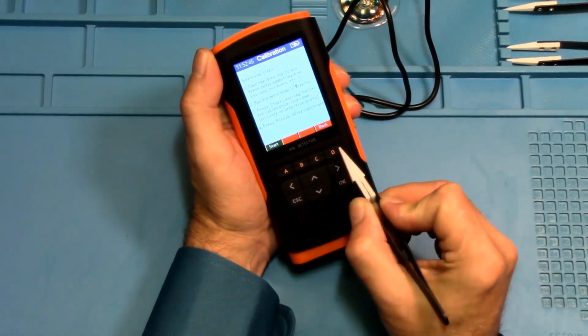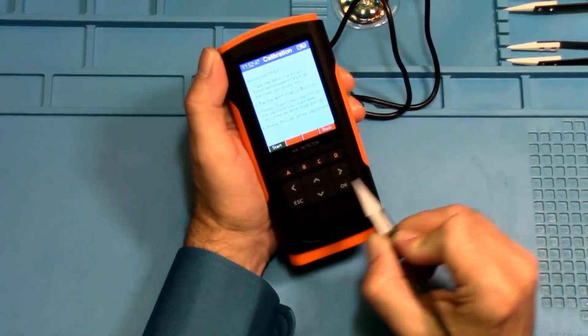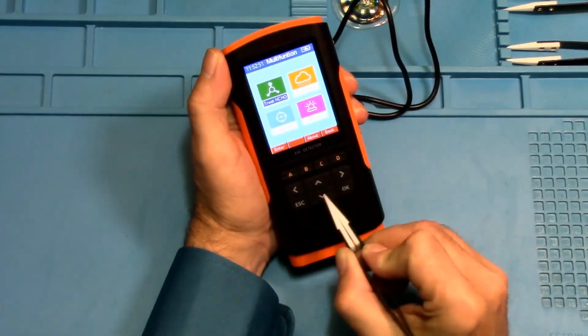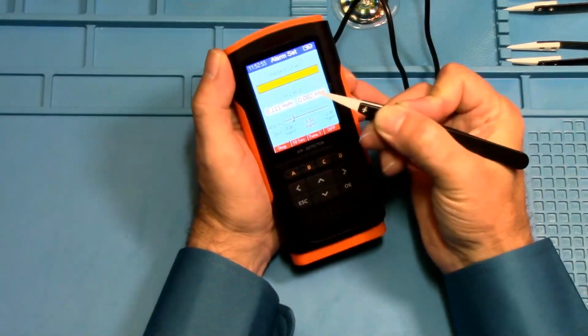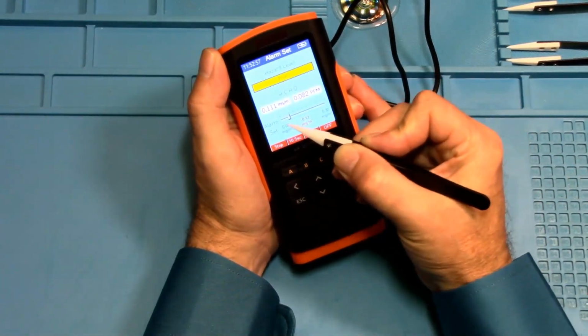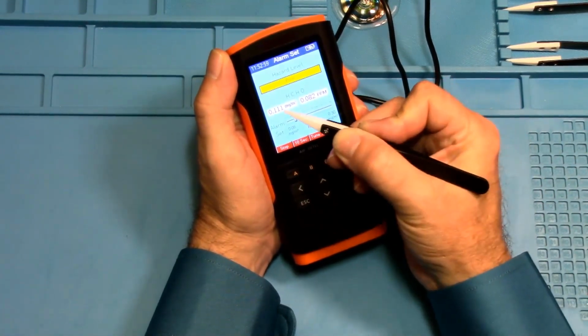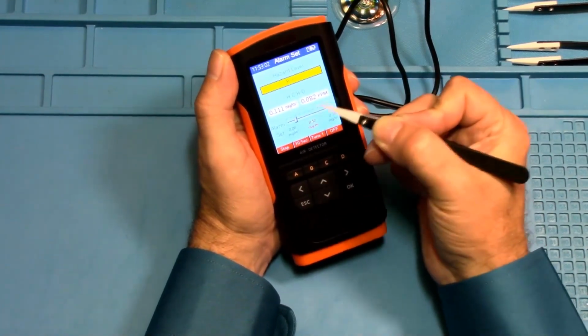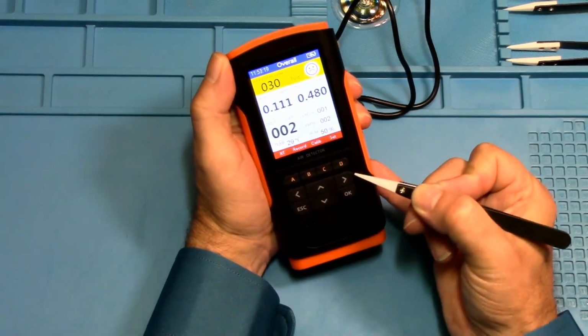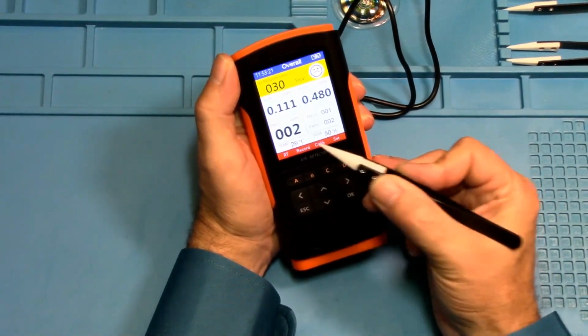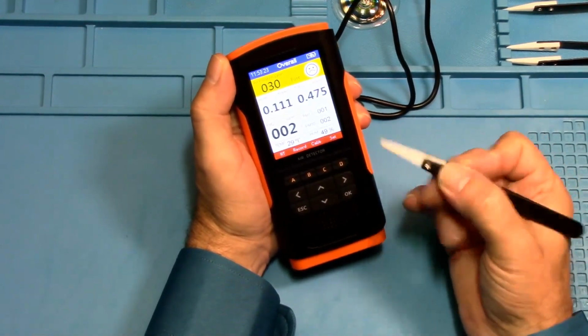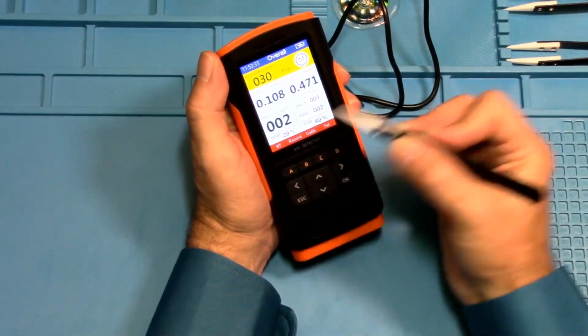And then you hit the D key to finish it and go out of that. And then alarm, you can go into that, and that allows you to set at what level you want the alarm to start alarming. There isn't anything in here for changing this to Fahrenheit. And for me, that sucks. None of my monitors, I even look at the temperature anyway. So that's no big deal to me.